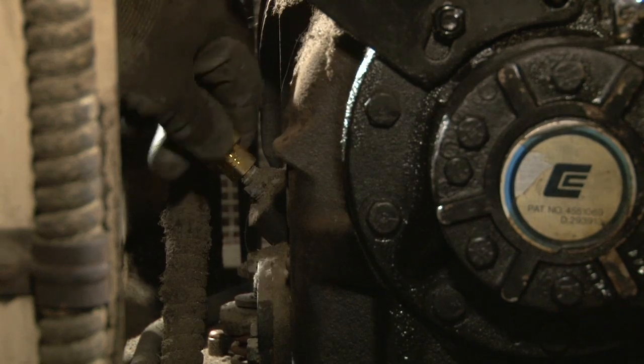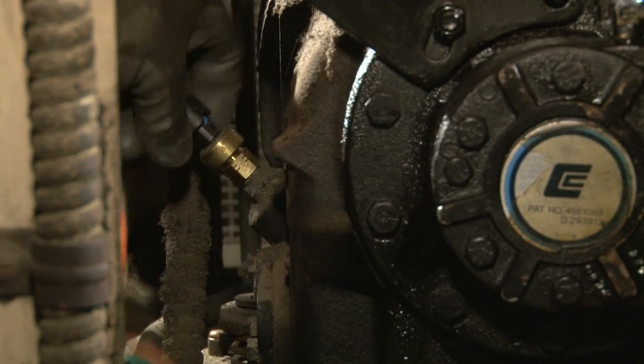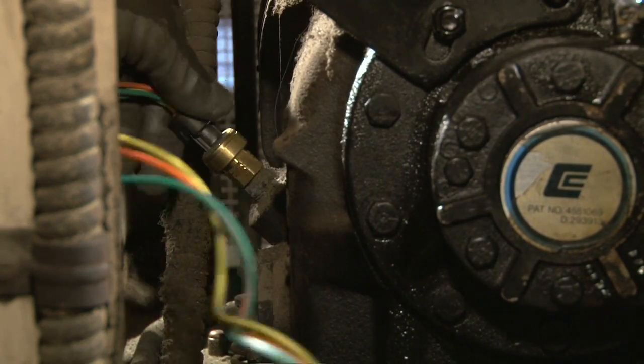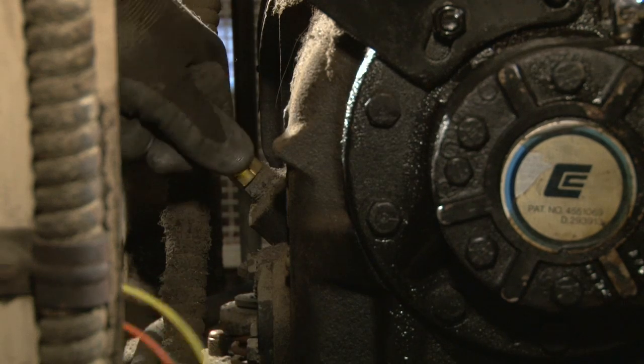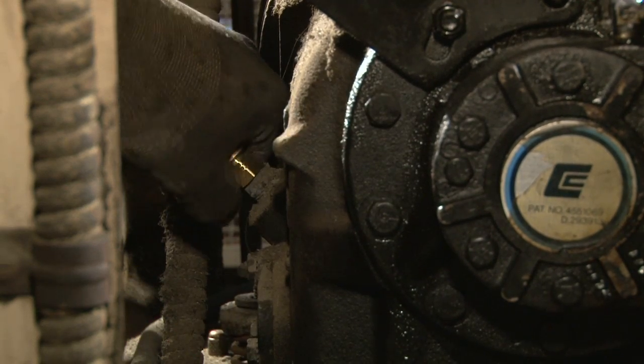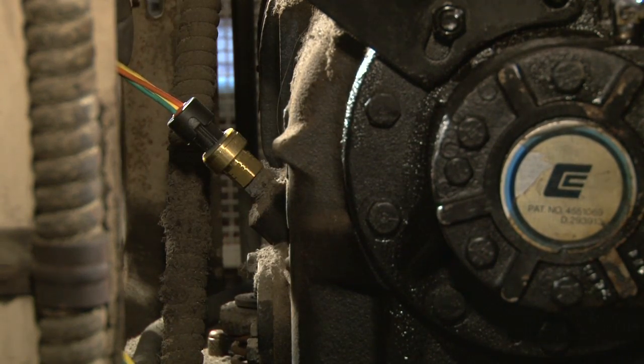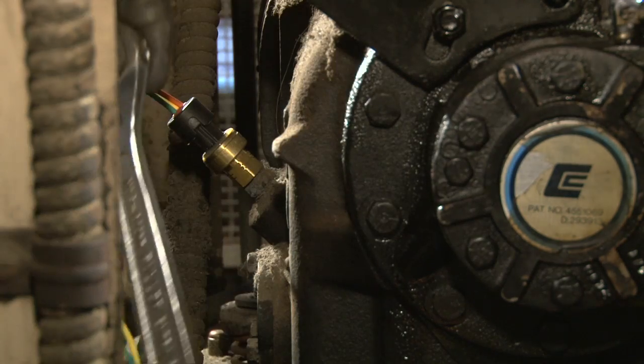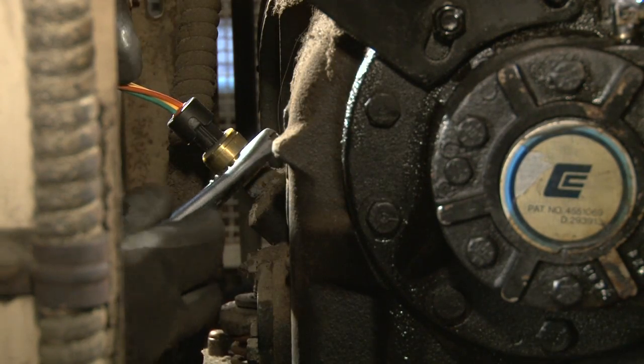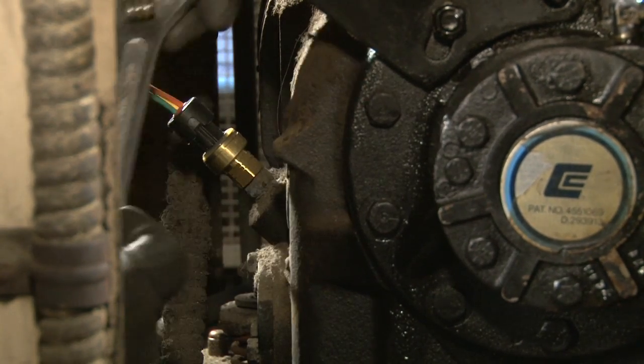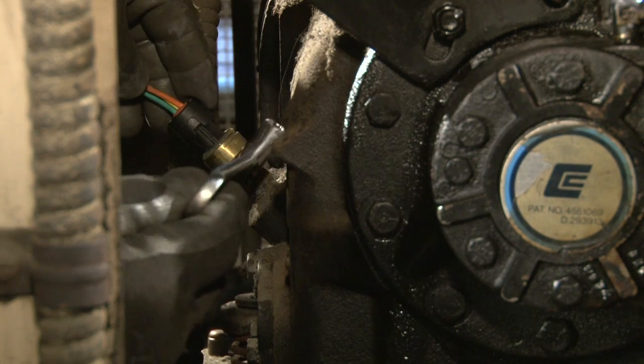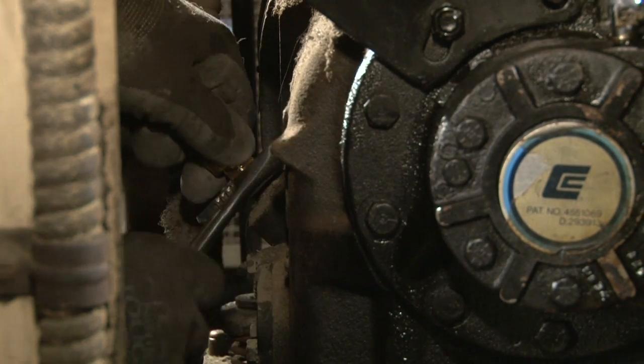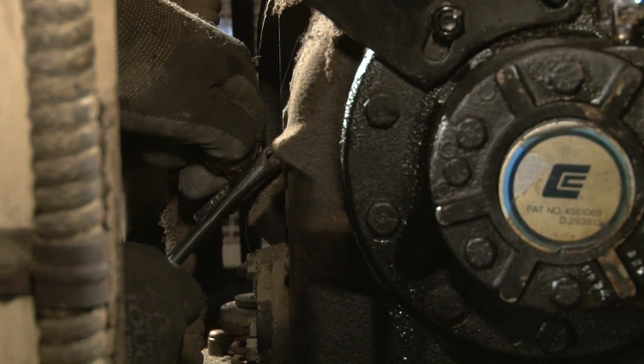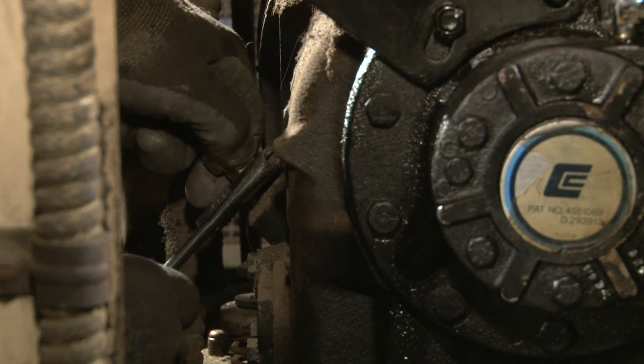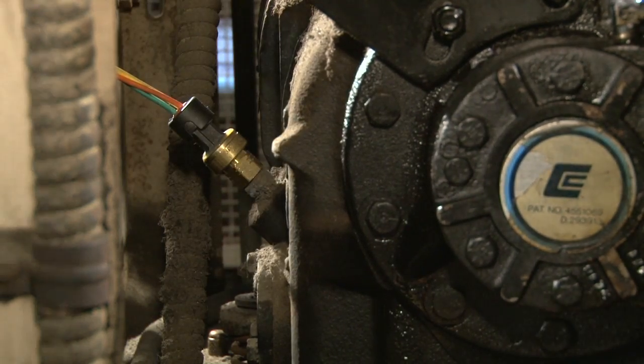Now the technician is installing the low pressure transducer onto the side body port fitting of the compressor. He had previously backspun the transducer approximately 7 times to ensure that the wire would straighten out when the transducer was installed. Here the technician is tightening the transducer using the small adjustable crescent wrench.